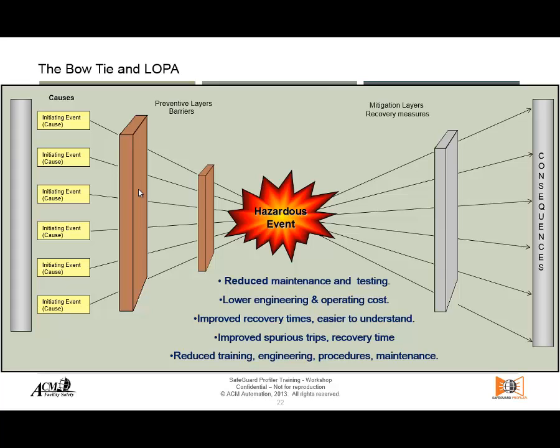We will also be improving the tripping behavior of those systems. If I had 10 things that could trip today, now I have only two — and I'm in better control. The amount of training required is reduced as well; there are only two or three pieces of equipment to train on, not 10 or 50. All this can be recorded and kept. The results of this layer protection analysis create recommendations that become the specifications for those safeguards — defining what type of safeguards we want, their characteristics, and how robust they need to be. Safeguard Profiler is the tool that allows us to do that.